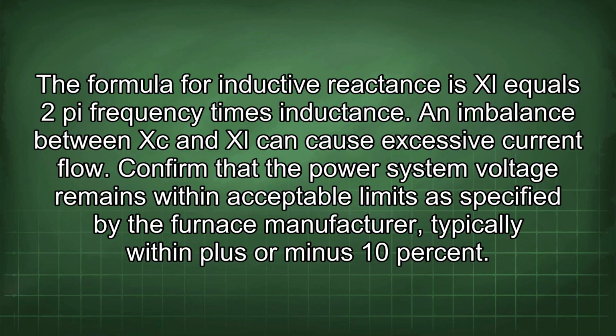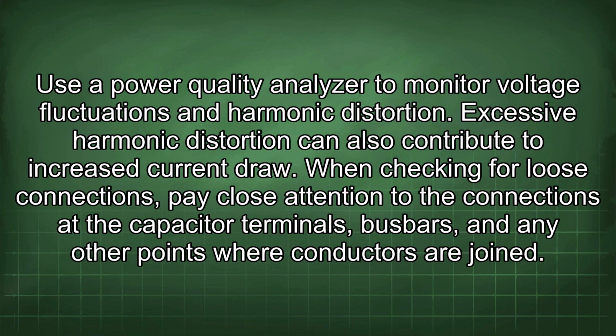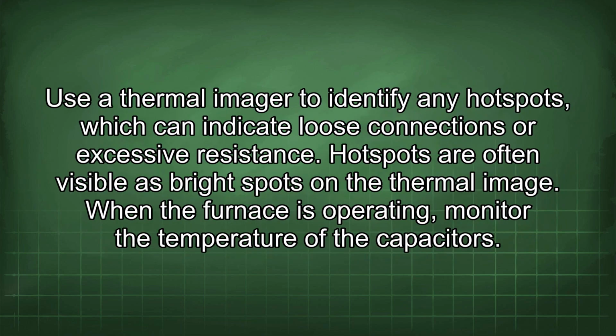Confirm that the power system voltage remains within acceptable limits as specified by the furnace manufacturer, typically within plus or minus 10%. Use a power quality analyzer to monitor voltage fluctuations and harmonic distortion. Excessive harmonic distortion can also contribute to increased current draw. When checking for loose connections, pay close attention to the connections at the capacitor terminals, busbars, and any other points where conductors are joined. Use a thermal imager to identify any hotspots, which can indicate loose connections or excessive resistance. Hotspots are often visible as bright spots on the thermal image.